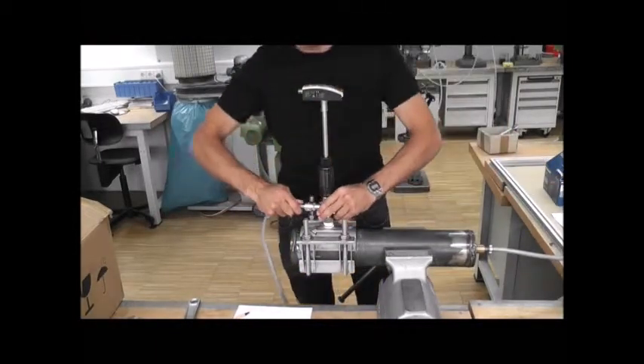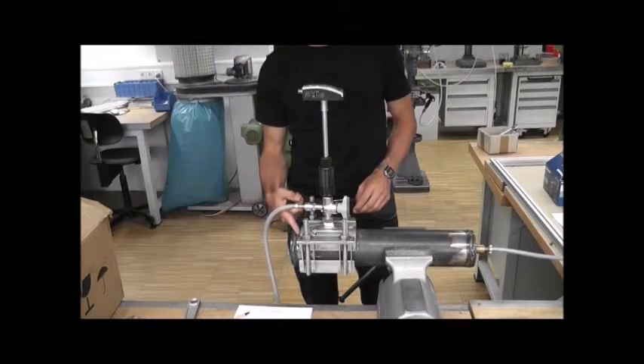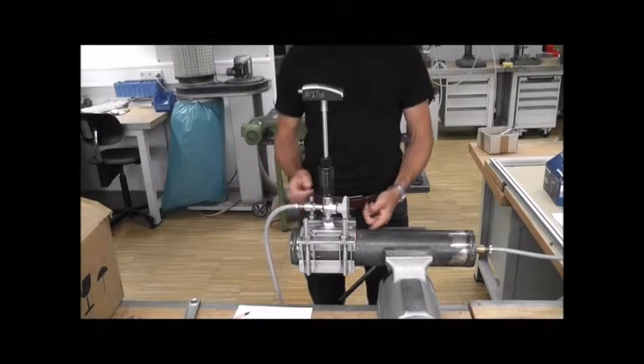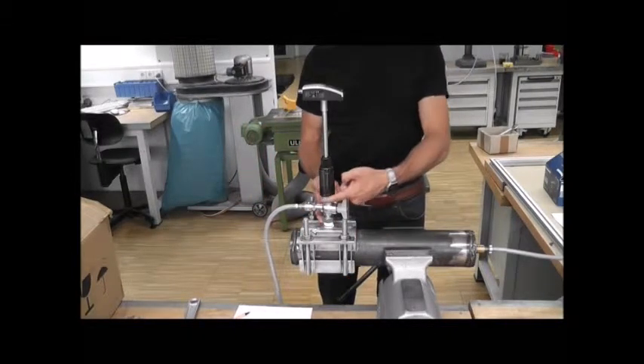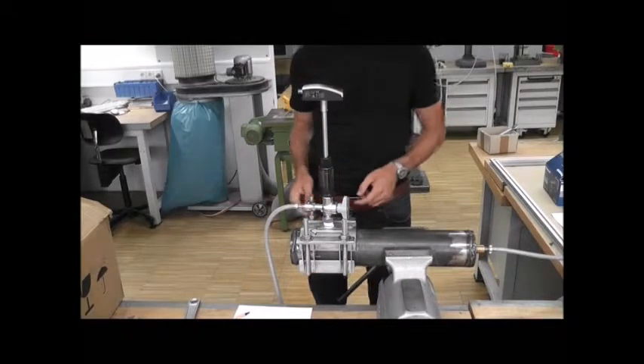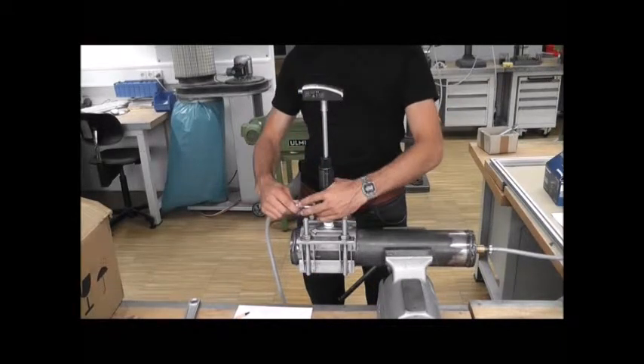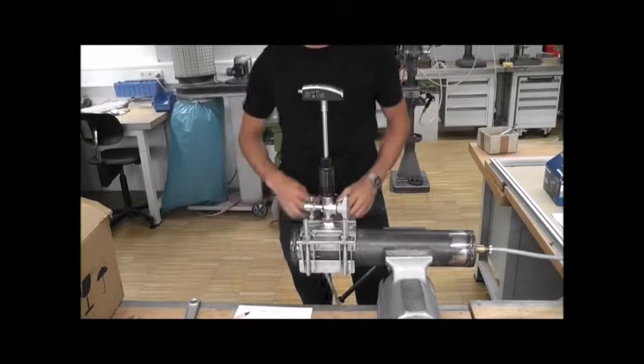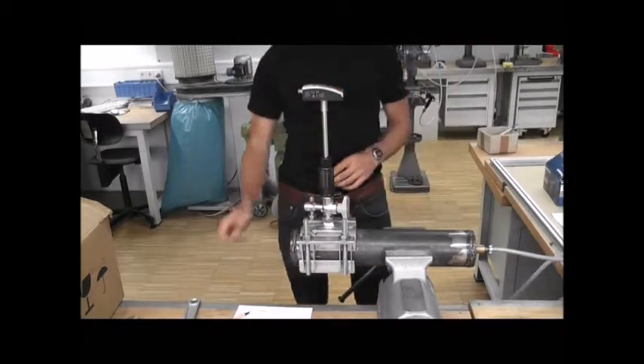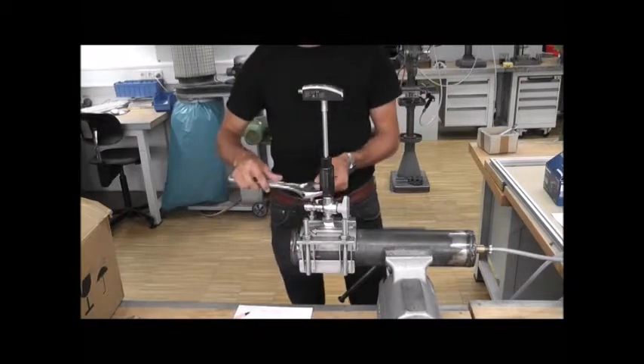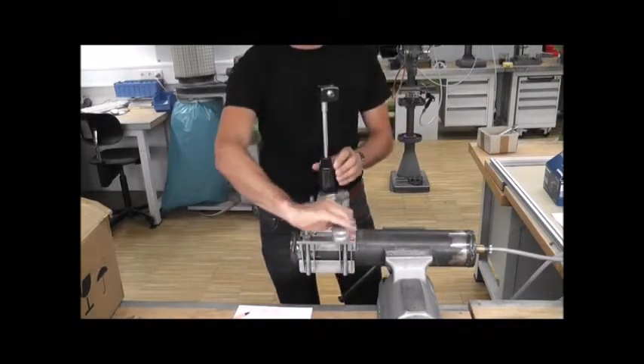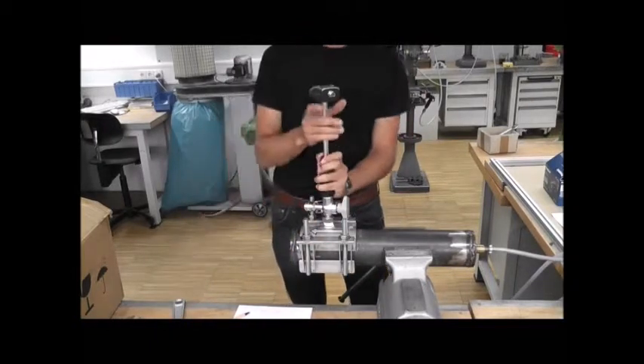Before you uninstall the transmitter, you should also prove if the tapping clamp fits leak proof on the pipe. Therefore, mount the compressed air hose to the ball valve. If you hear no sound of the compressed air, the tapping clamp fits leak proof on the pipe. The last point is to uninstall the transmitter.